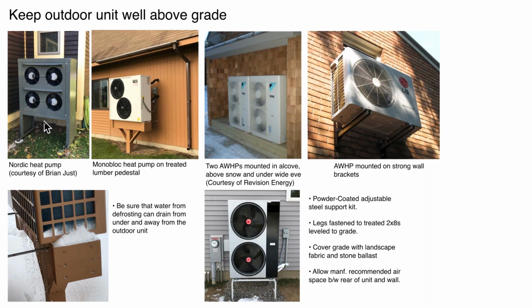We want to get it up not only away from snow, but by getting that unit up, we get it away from grass clippings, leaves, bugs, you know, the dog going out there and thinking it's a hydrant, that type of thing. And you can see these are different ways of supporting the heat pump. This is actually one where they put a couple units in and they actually built a little alcove. It's up on some treated lumber here, and it's got an overhang over it to protect it from the rain. This is a low capacity unit, a split system, and you can see it's up on wall brackets. There are brackets that are out there that have the strength to do that.